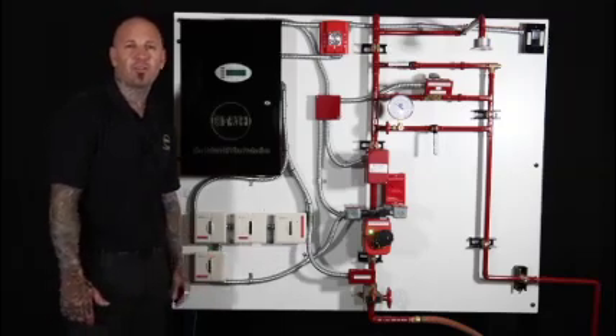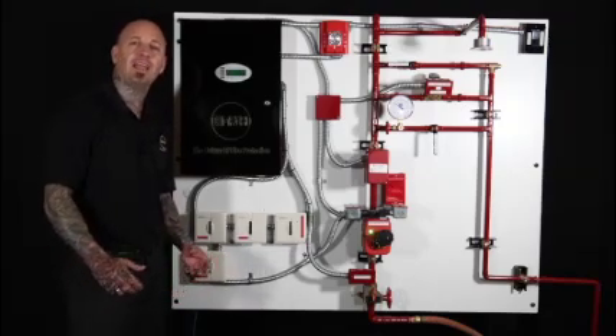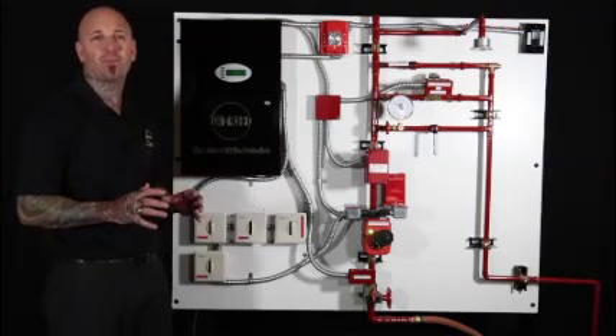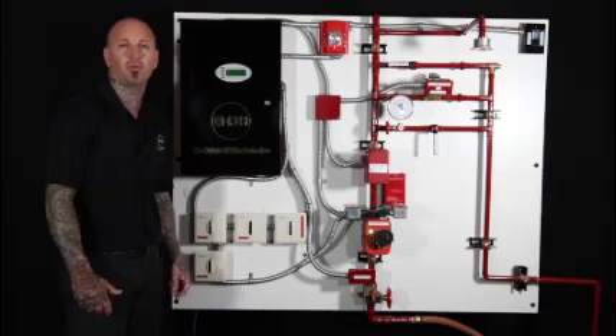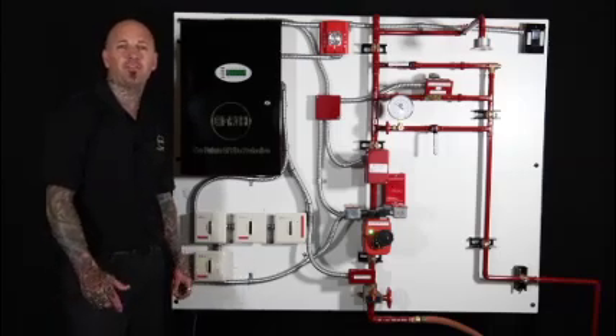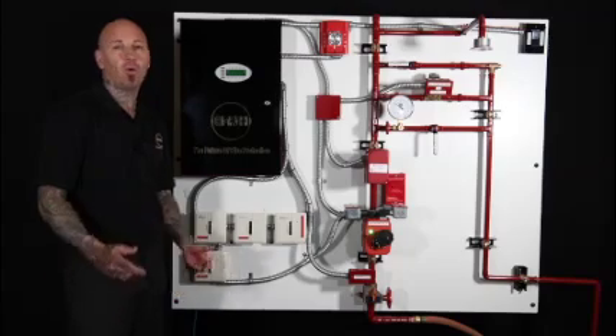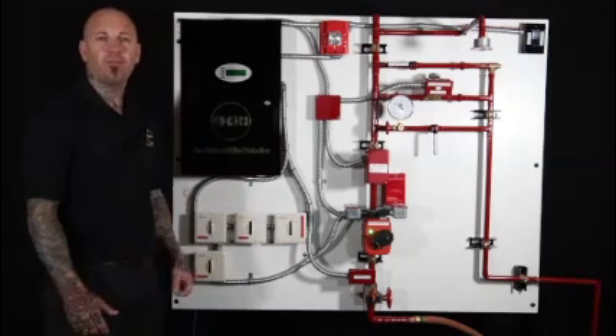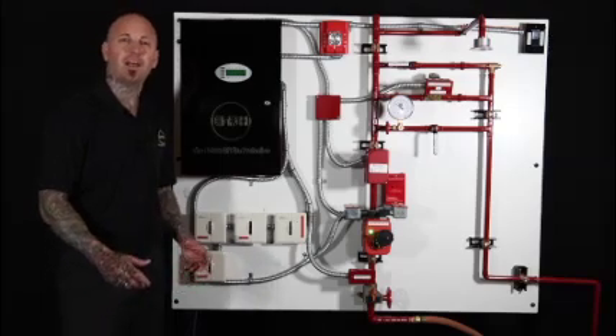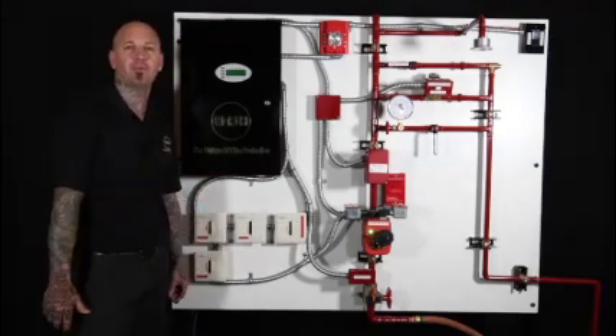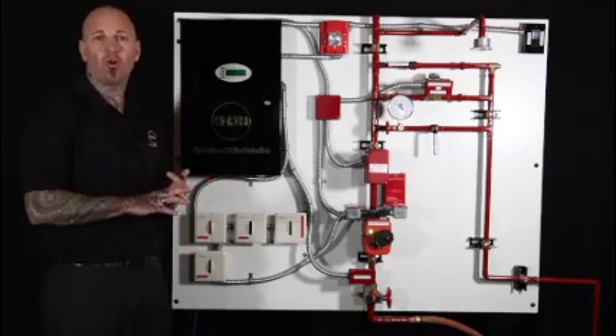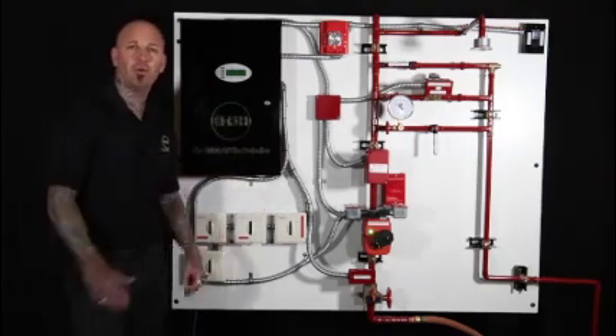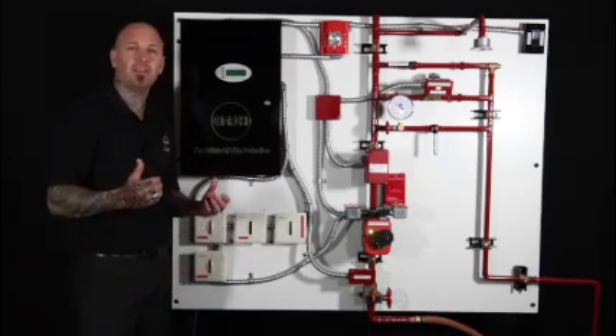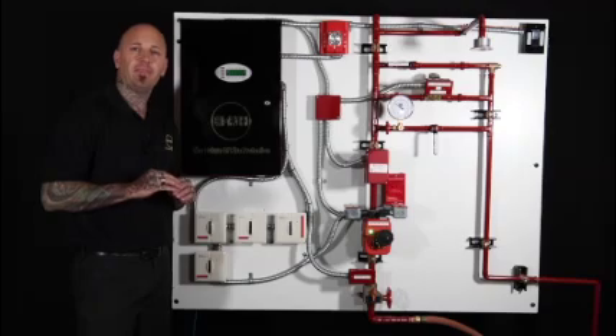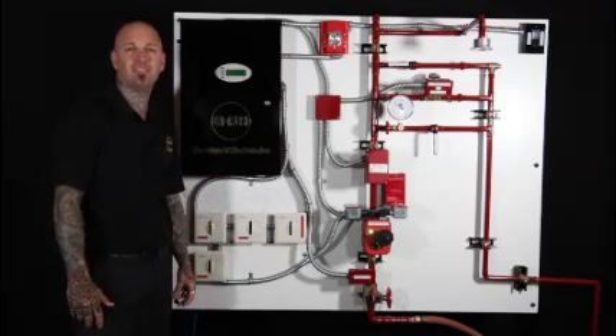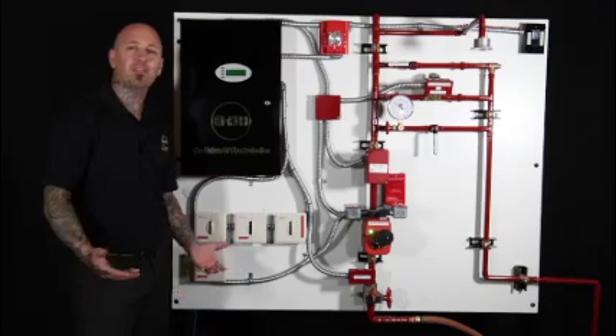With over 20 years experience in this industry myself and my family with over 80 years combined, I've heard countless stories, and there have been numerous times I've been called out on an emergency call where the sprinkler pipe had been damaged or failed due to natural causes or simply just human error. The water damage in these cases was so extensive, the entire buildings or houses had to be evacuated. The drywall, carpet, hardwood floors, and other miscellaneous interior components had to be removed due to the amount of flooding that had occurred. Now keep in mind, there was never a fire in any of these instances that set the systems off. It was merely a simple accident.